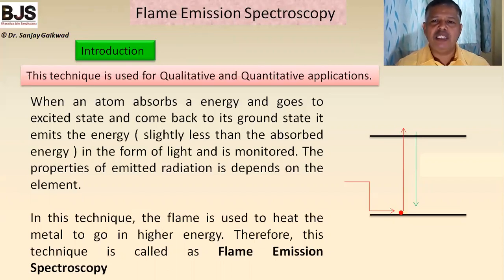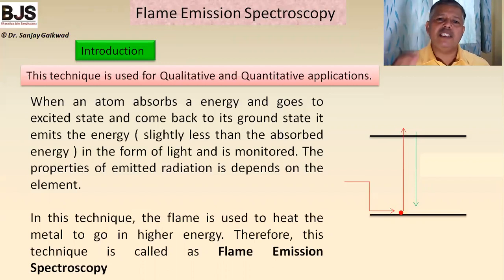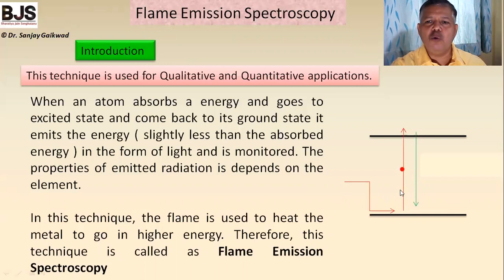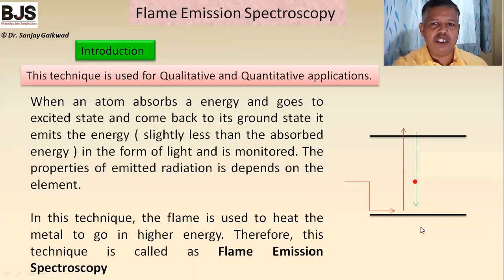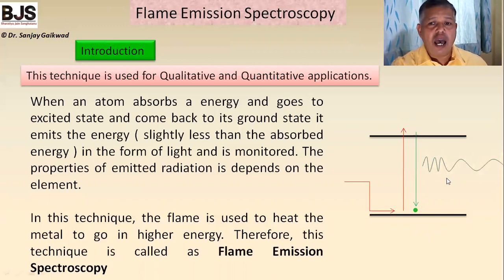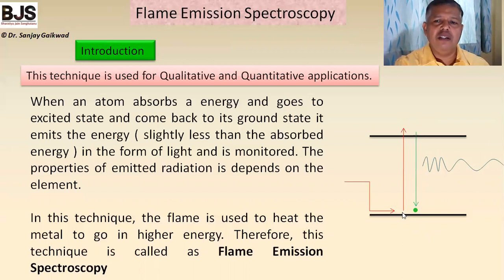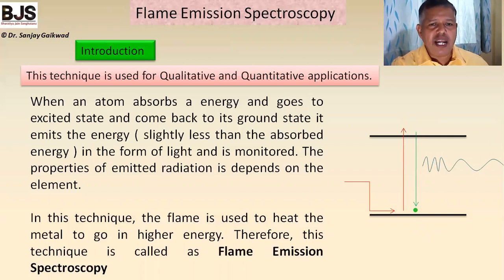In this technique, the atom or molecule present in the solution absorbs heat energy from the flame and goes to the excited state. After a certain time it comes back to the ground state, releasing the absorbed energy in the form of light radiation. The emitted radiation is at a slightly different wavelength than the absorbed radiation because some energy is consumed in the excitation process. This is the basic principle of the flame photometer.